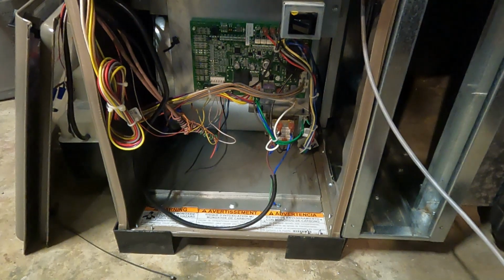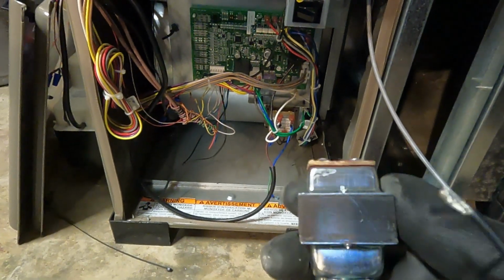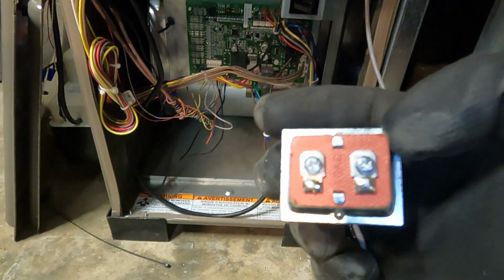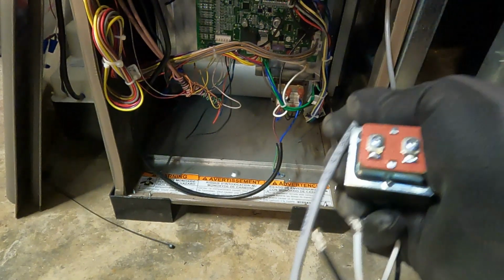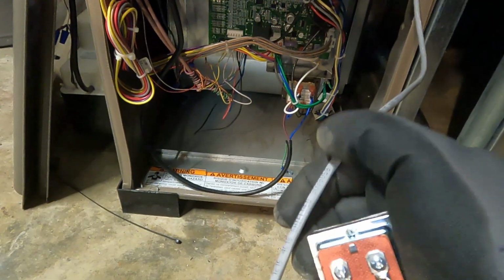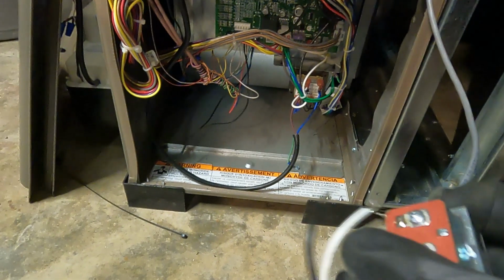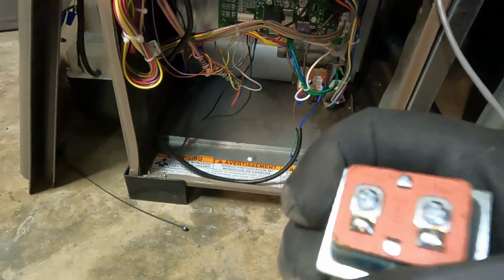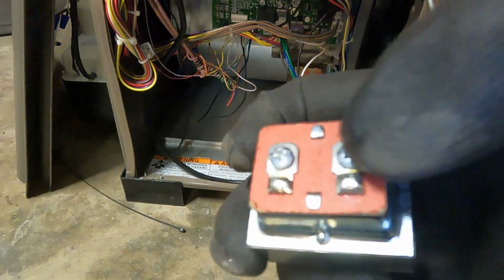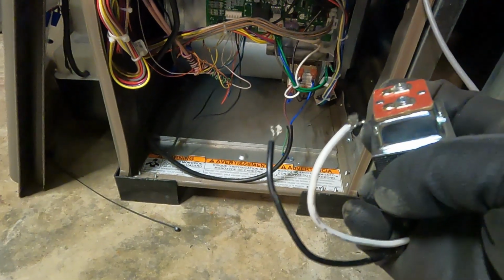Alright, so in the kit for the humidifier, they include a little transformer. So from the previous step we ran our wire, so all I'm going to do is tie my red and white wire coming from this to my two wires here on the top. Those are my low voltage terminals. My two high voltage terminals I'm going to tie into the board here. There's specifically a spot for the humidifier, let's see if you can see that. It's abbreviated HUM, it's the bottom terminal right there.